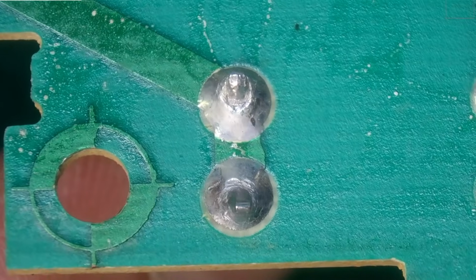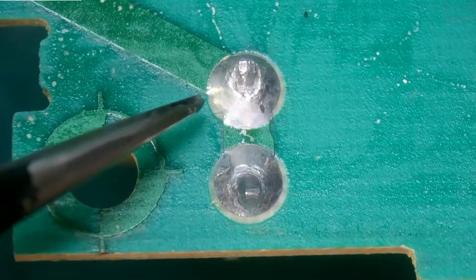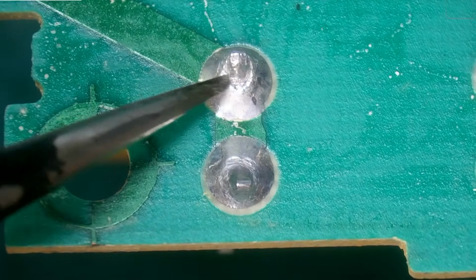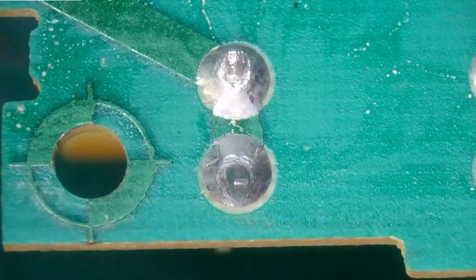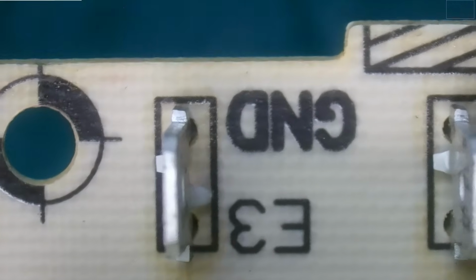So we have a few of these connector spade pins on the circuit board. We're going to want to inspect those on the back. And sure enough, look at that - this one over here is starting to get severely cracked, and if not addressed, will cause an issue down the line. That one looks to be our ground spade pin.